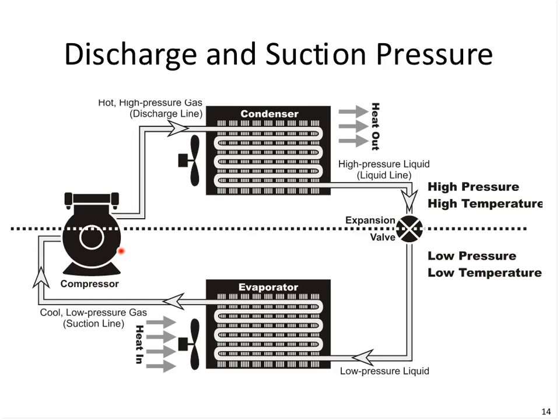the compressor. So sometimes we have multiple compressors or variable speed or slide valve modulating the flow of refrigerant, because what we want is the compressor to match the flow of refrigerant as the metering device. So if only half of the refrigerant is needed, then only half of the compression is needed. And the controls would maintain that to keep the space temperature and then modulate the flow of refrigerant. And as mentioned earlier, we can't have these large compressors turning on and off repeatedly.